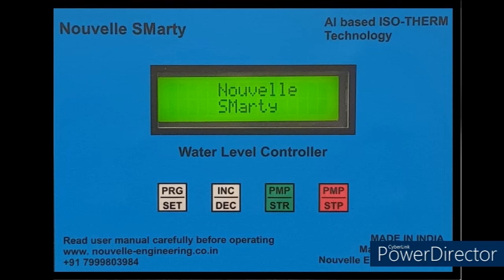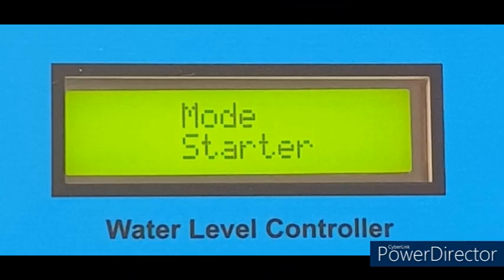Parameter values will be saved in the EEPROM of the system and are retained even if there is no power. Repeat the process if you want to change any other parameters. New values will be effective only after restarting the WLC panel. Caution. Do not forget to set the FDR mode, either DOL or starter. The new value of FDR mode will only be effective after restarting, and do verify the same on the main screen. Warning. Wrong selection of FDR mode may cause serious injury to a person or damage to the pump. In any case, the pump panel should not be operated in incorrect FDR mode.